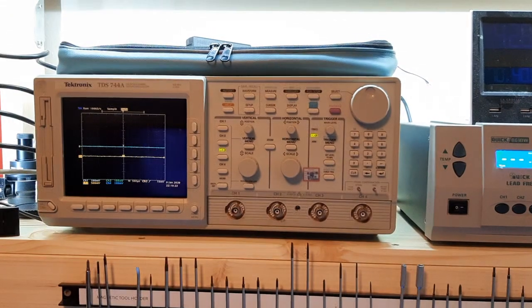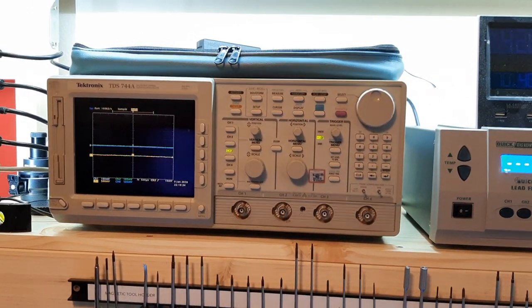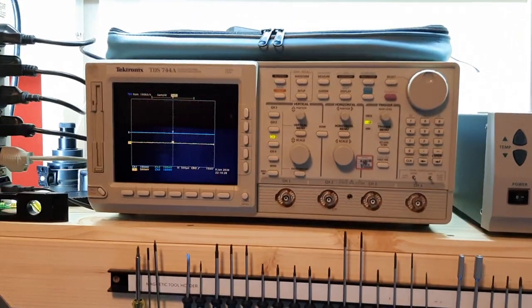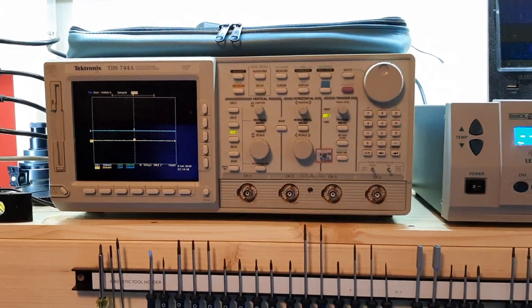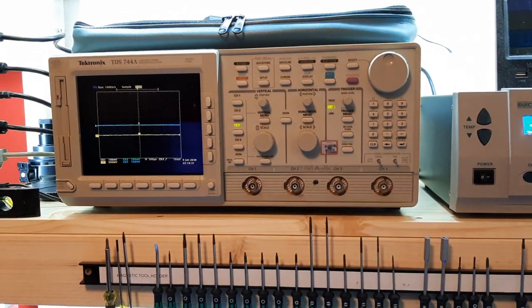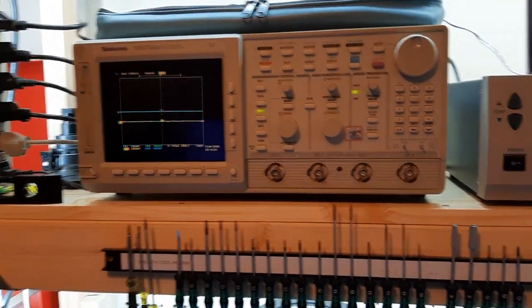Can we focus? There we go. 500 megahertz, 2 gig sample. And most importantly for the 80s and 90s Tektronix scopes, maintainable. Easily repairable, full schematics in the service manual available, and you can get parts, you can replace it yourself.